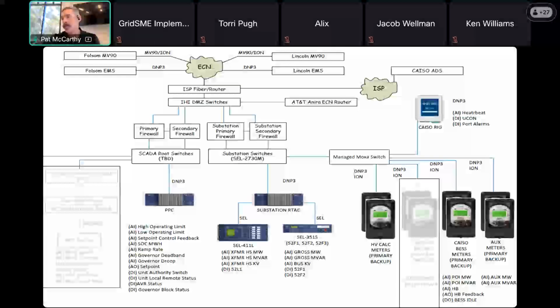Since this site represents batteries and PV, it's important to note you may have different point-to-points for different resources, because those technologies may come online at different times due to project construction phasing. You could test your PV if ready in February, and your BESS comes online in March—those would be two different appointments. If the rig can be shared between resources, or you have two rigs, you'd have two different documents like this for each resource. That depends on how you're configuring and designing your system.